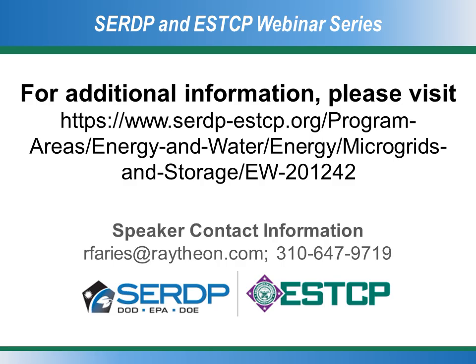So there are a lot of protocols and standards for the small devices that are used. For this one, the microgrid controller and what we were interacting with on the battery was an OPC interface for those two particular elements. Because a lot of devices already existed with their own protocols and interfaces, there's Modbus, and we also used analog signals and digital signals throughout. But it was predominantly OPC, fiber over Ethernet, things like that, as well as Modbus type interfaces, both Modbus IP and Modbus RTU.